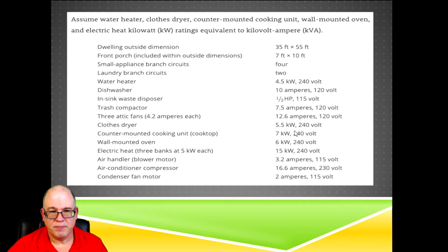We're right here. Water heater, 4.5 kW. Okay, so again, kW, we need it in VA. So 4.5 times 1,000, or you can just look at it and see the K. You'll learn that K is 1,000. So it's 4,500 watts, which is synonymous with VA, and we need VA. We're going to do calculations in VA.